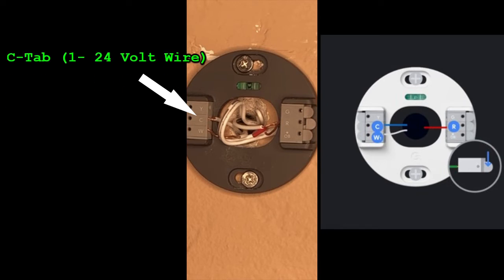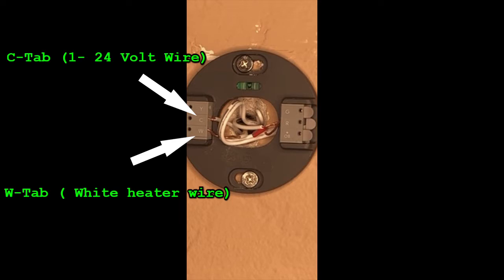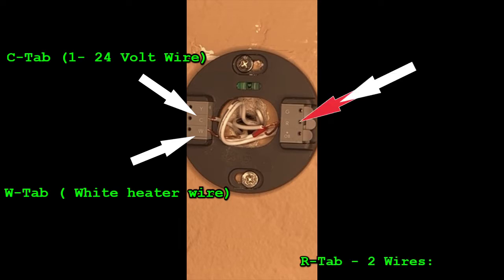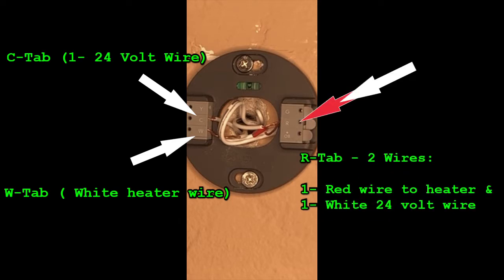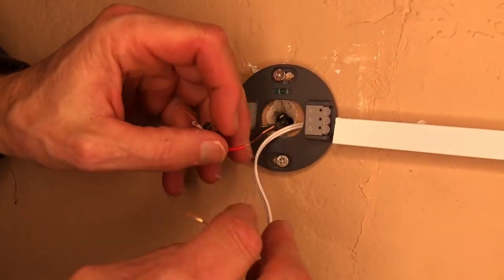Here is the wiring diagram. You have four wires. See on the upper left, it says C tab. So you take one of the 24 volt wires from your adapter that you plugged in. It goes to the C tab. You go down to the bottom on the left, it says W tab. The white heater wire, that wire goes to the heater, you want to plug it in there. Then on the right side, you only have one slot, the R slot. You're going to have two wires there. One is the red wire that goes to the heater. And the other one is the white wire that goes to the 24 volt adapter. You're just going to have to spin those two together really, really tight and slide them in the slot. It took me a few tries, but it was successful. This is a really simple wiring diagram.